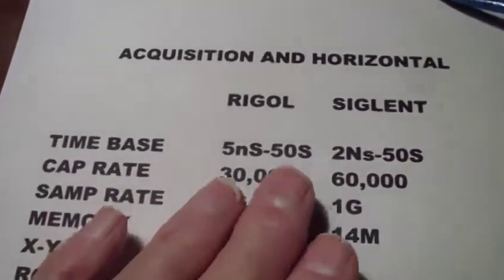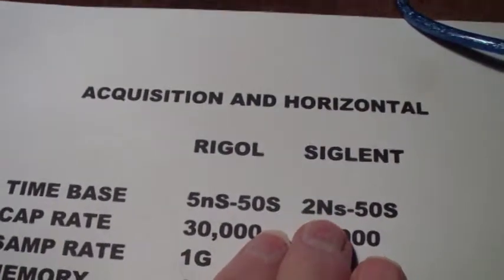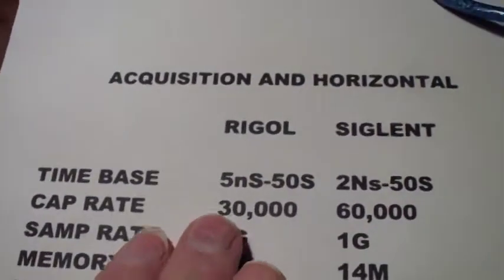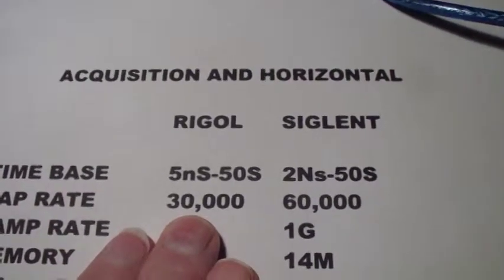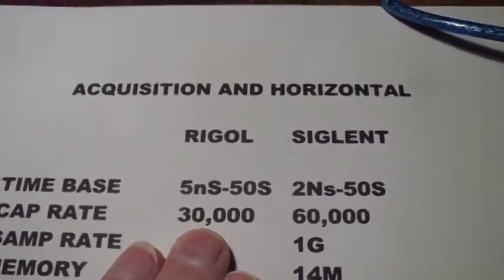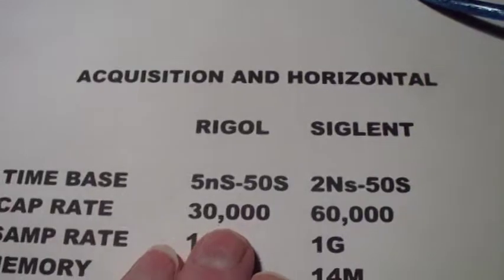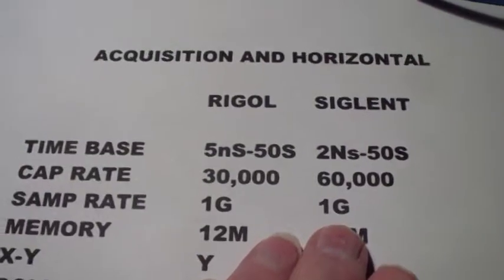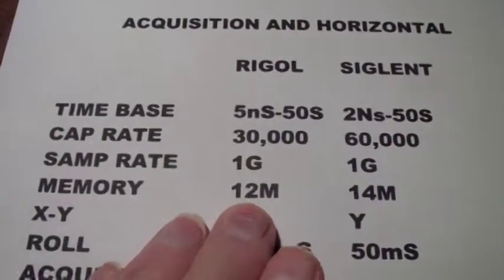Here are the published specifications — I haven't verified these. The Rigol time base can go down to 5 nanoseconds per division and up to 50 seconds per division. The Siglent can go down to 2 nanoseconds and 50 seconds. The capture rate — these are published rates and will vary greatly depending on the time base selected and trigger type. This is a maximum of 30,000 waveforms per second for the Rigol versus 60,000 for the Siglent. They both sample at 1 gigasample per second.